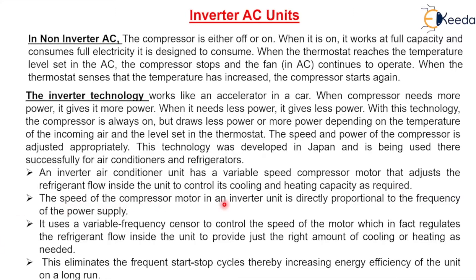The speed of the compressor motor in an inverter unit is directly proportional to the frequency of the power supply. It uses a variable frequency drive to control the speed of the motor. As the load changes, the speed changes accordingly. This eliminates the frequent start-stop cycle, thereby increasing the energy efficiency of the unit in the long run.